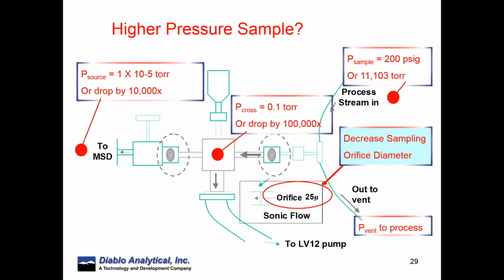Now, let's say that in your application, you're going to go to a higher pressure. So in this case, in the upper right, you can see that we have a 200 PSI sample. What we can do is decrease the diameter of the first orifice. In this case, we've gone from 30 microns to 25 microns, and that's simply by spinning a VCR fitting open and putting in a 25 micron orifice. And at 200 PSI across a 25 micron orifice, we still reach 0.1 torr. So the rest of the system works the same, even though your sample pressure is actually higher.